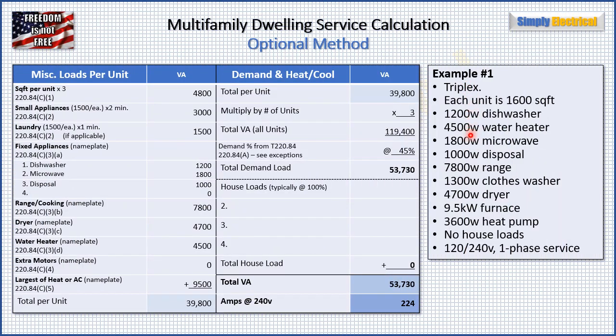We start in the left-hand column. Square footage of each unit is 1,600 square feet. Multiply by three, that gives us 4,800 VA. For small appliances, even though none are called out in the example, they are required by code — two minimum at 1,500 VA each, so 3,000 VA. For laundry, since we have a clothes washer in the unit, we must add a circuit. Even though it says 1,300 watts, we put 1,500 minimum for this calculation.